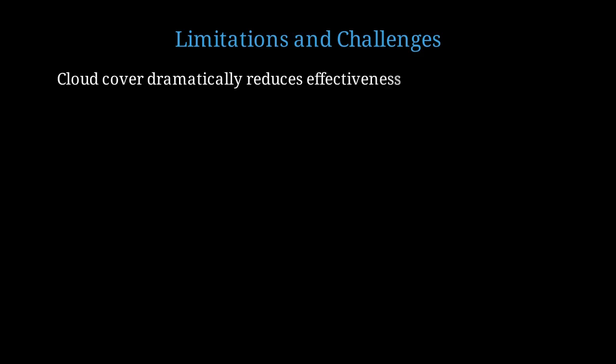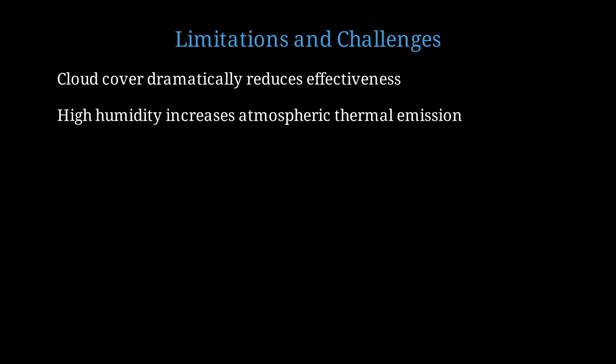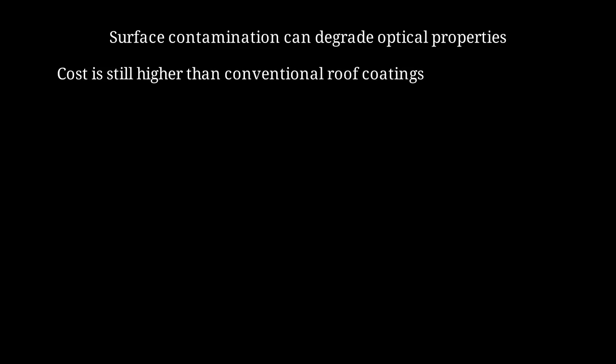Of course, this technology has limitations. Let me be clear about the challenges. Cloud cover dramatically reduces the cooling effect because clouds emit thermal radiation back toward the surface. This technology works best in arid, clear sky climates. High humidity also reduces effectiveness because water vapor increases the atmospheric thermal emission in the 8 to 13 micrometer window. Dust, dirt, and biological growth can degrade the optical properties over time. Maintaining high solar reflectance requires keeping the surface clean. Currently, the cost of advanced radiative cooling coatings is higher than conventional white roof coatings, although this is improving with scale.